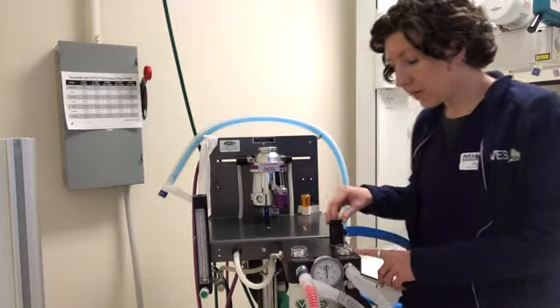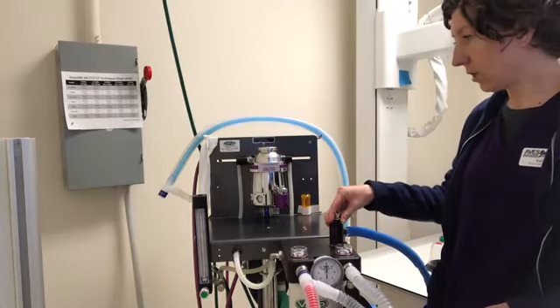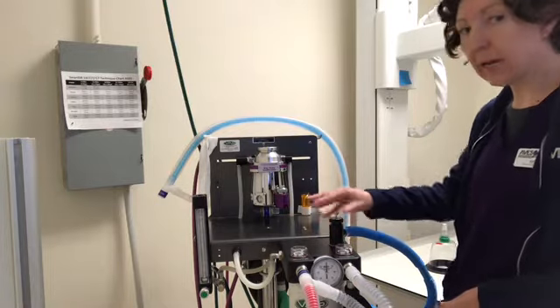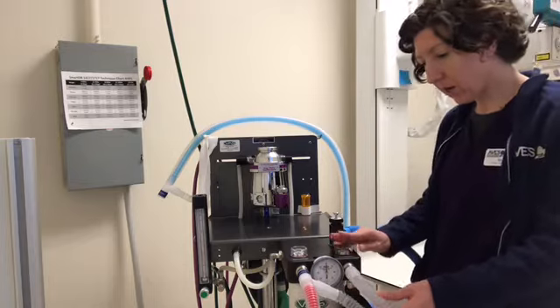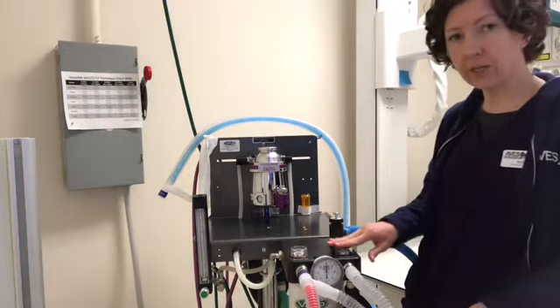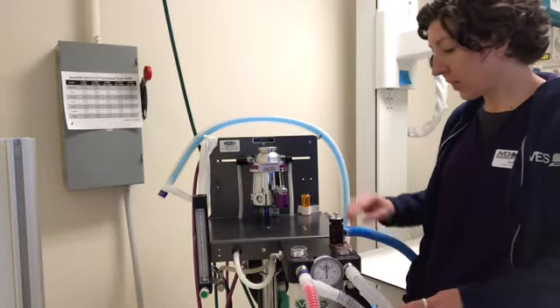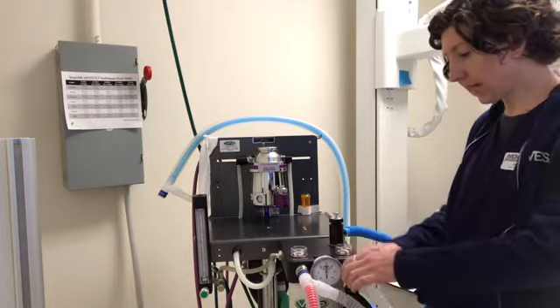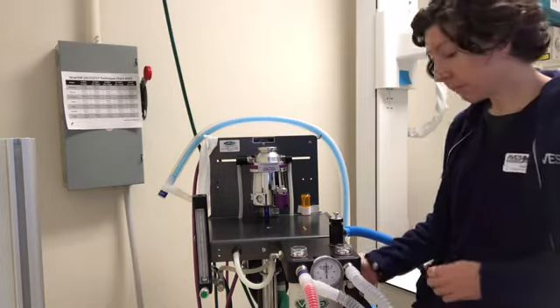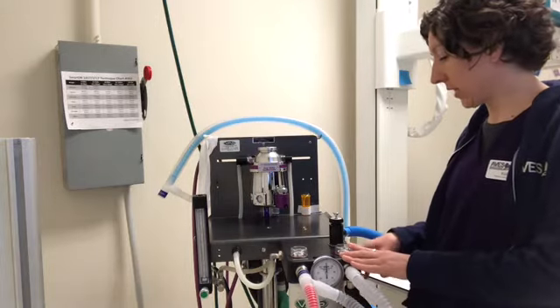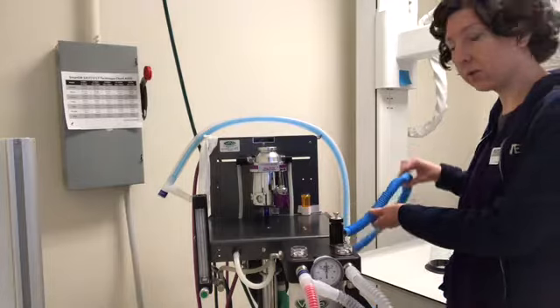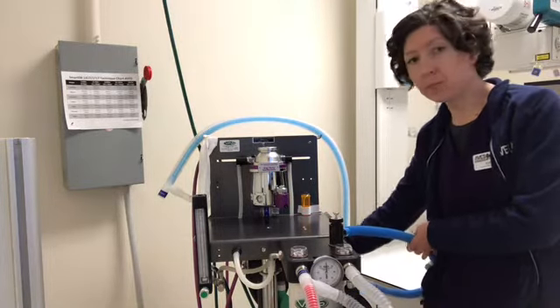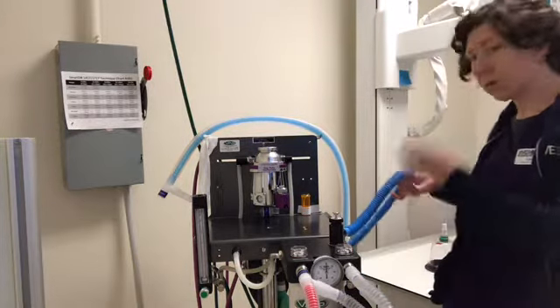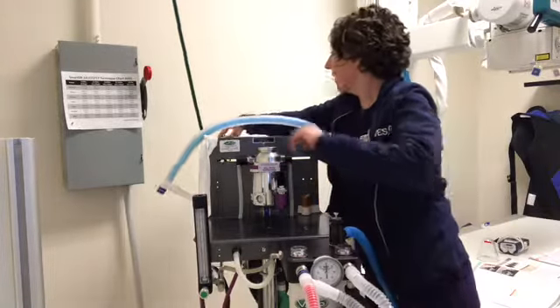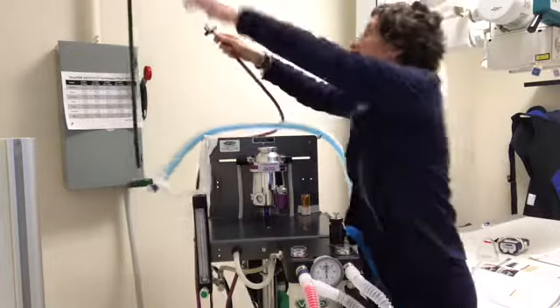The pop-off valve allows the excess oxygen and inhalation anesthetic to exit the system. So when the patient exhales, you will see on this little window, this little lever here will rise and fall with the breath, and the exhalation goes through the canister of soda lime, which absorbs the excess CO2. And then it exits, goes up through here, the pop-off valve, and then through this scavenging tubing and exits the system through an active scavenging system. So it goes through this tubing here, and then our scavenging system is this pink line that is hooked up here next to the oxygen port.